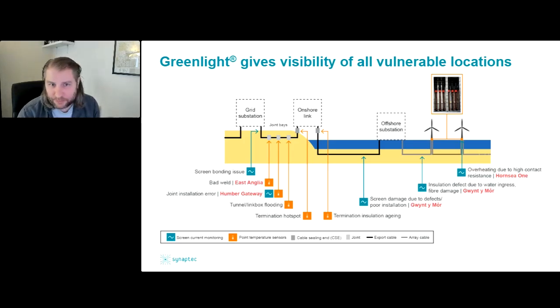For example, the bad weld event for the East Anglia 1 export cable led to a localized temperature increase at one of the joints onshore. Simply putting a temperature sensor there, and Synaptec temperature sensors are very small and passive, they just need to be able to connect to a fiber, would have seen the event emerge as it's happening, and allowed some options for mitigation. For example, the power flow in that cable could have been restricted to, say, 80% of what it would normally be able to achieve, and that would prevent it from overheating. And it at least keeps the system running before a repair can be scheduled.